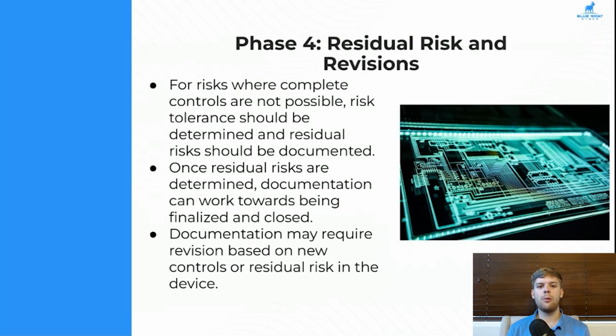The next thing is we'll look at residual risk and revisions. So if we have any risks where a complete control is not possible, our risk tolerance is going to say whether or not this is acceptable and how we need to document it. If there's any significant risk to the end user or to the patient, that needs to be communicated in the cybersecurity labeling, and residual risk should be captured in our risk management report. We'll have all of this information, and that is essentially what is left in the product. Now, when we identify our risk tolerance, everything left in the product and all of the vulnerabilities in combination should not be above what we have already determined to be our maximum level of risk.